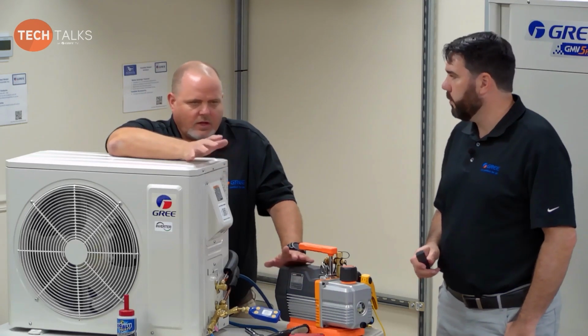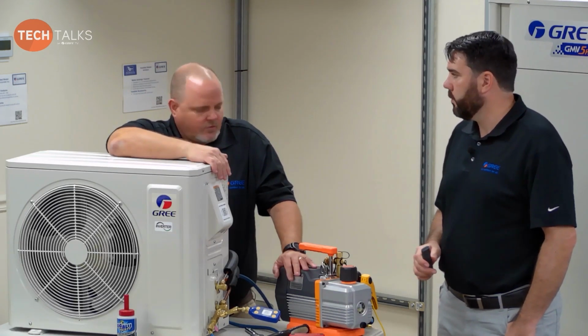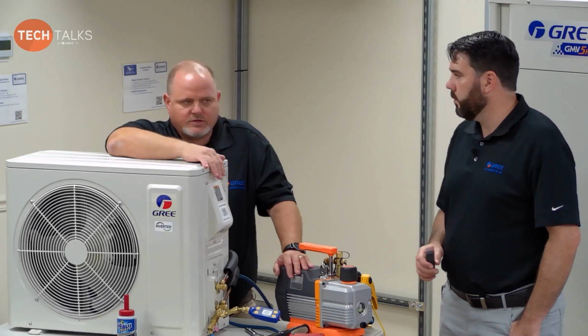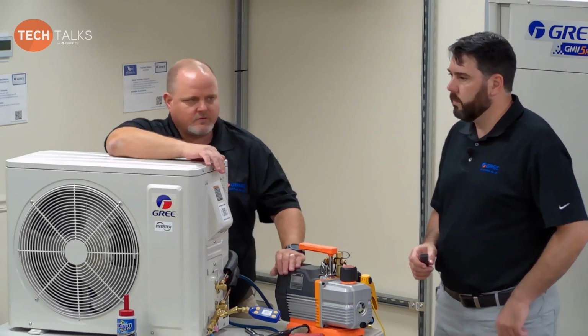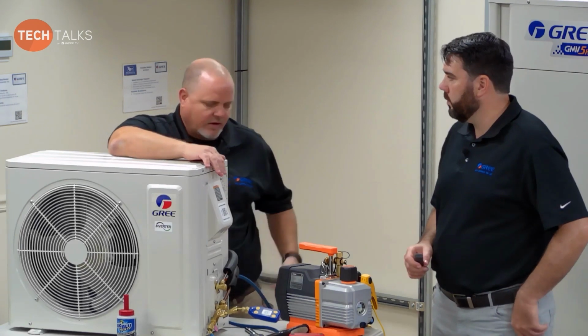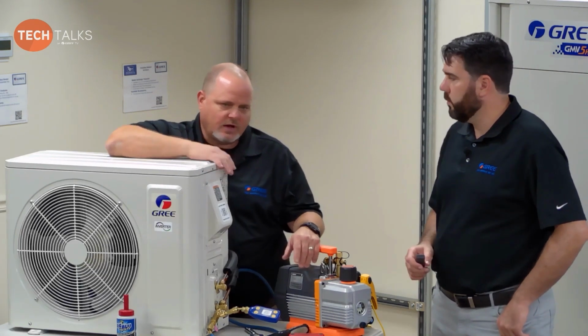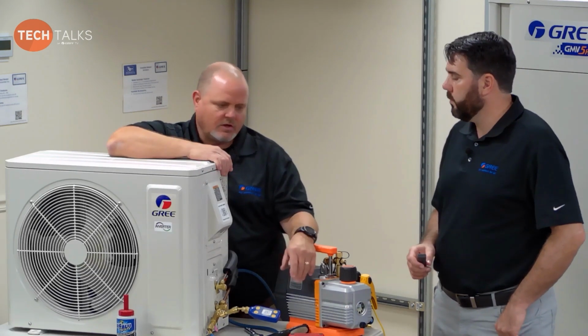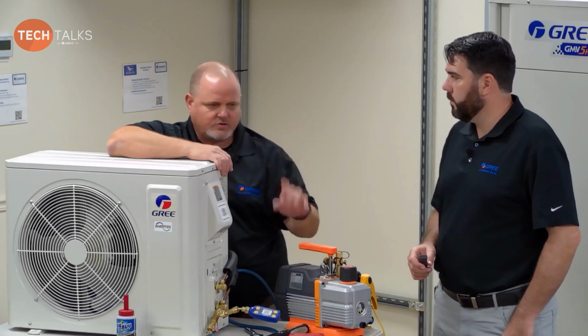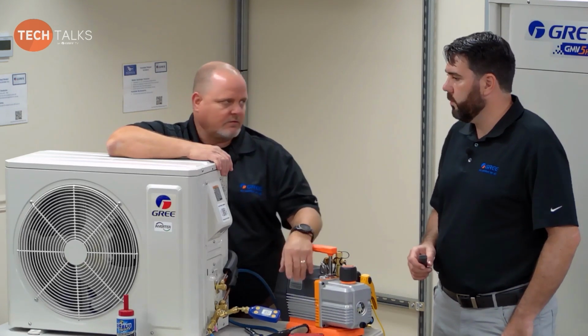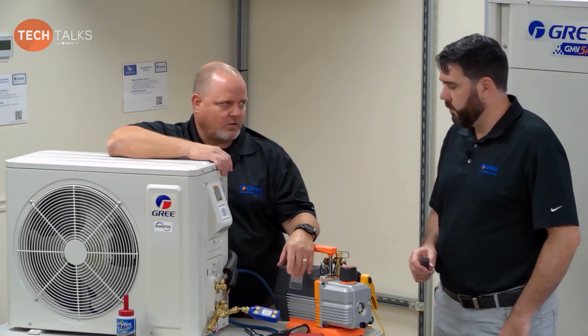Again, you're only pulling lines and coil down. We don't have to do this whole triple evacuation and stuff like that, which we will talk about in service. You strictly just need to pull a vacuum. You do your pressure test with the nitrogen. You make sure you don't have any leaks. You let the nitrogen back out, and we do our evacuation on the lines and coil.